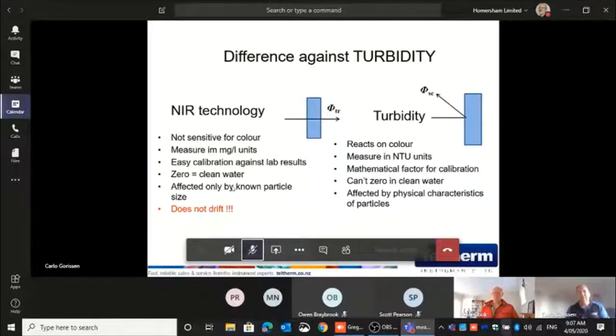What's the main difference against turbidity? Well, first of all, we don't see color. So if you got water or you got tea, for instance, if we put our sensor in tea, it will come up with 0. You put a turbidity sensor in tea and it just goes nuts. That's the big difference with our sensors. So for dairy people, if you want to see color, if you want to see milk escaping or something, we can't see that. We only see solids.